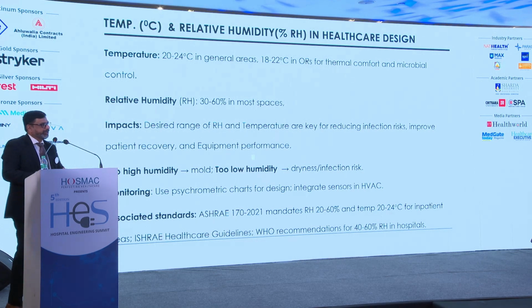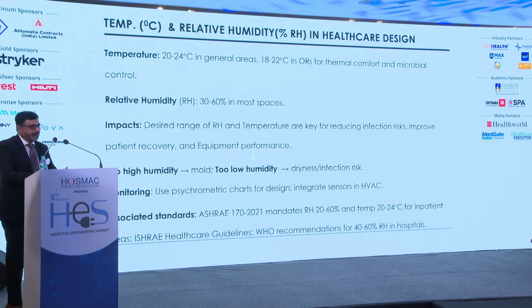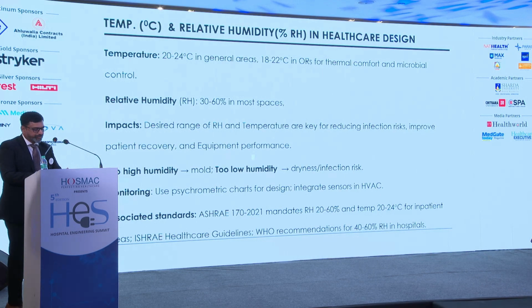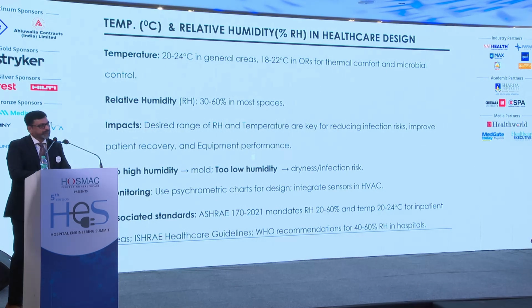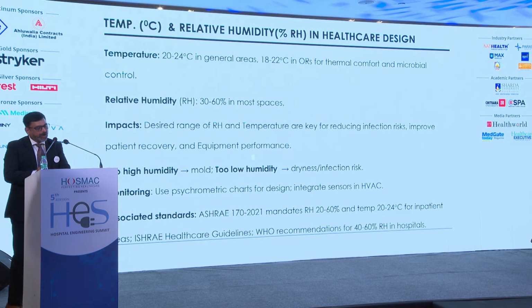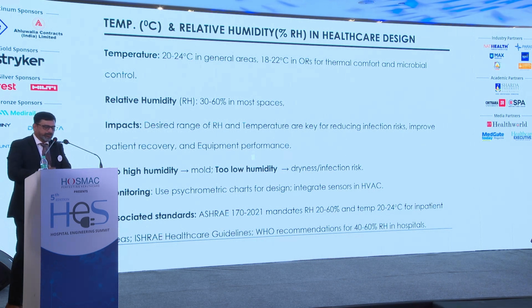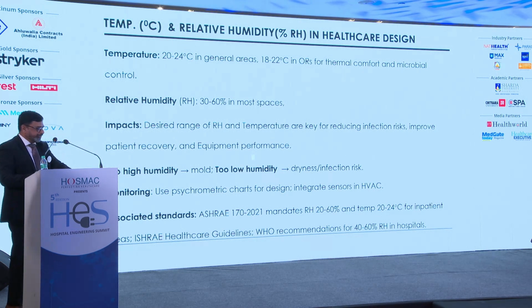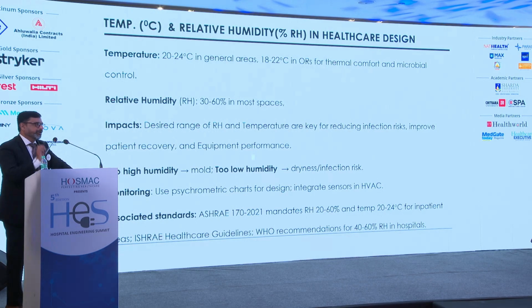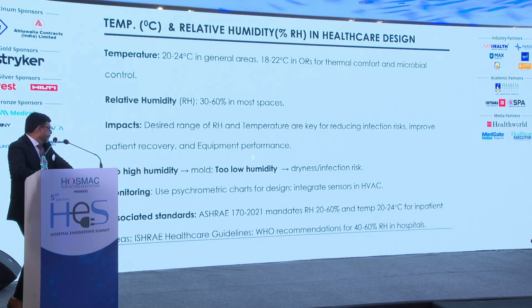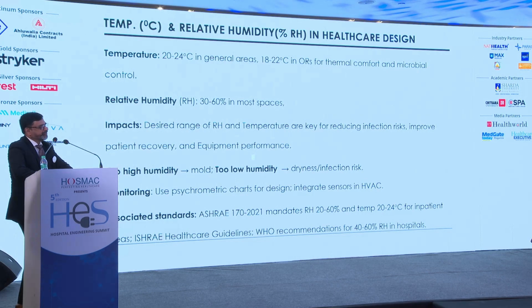So relative humidity is one of the major parameters for clinical spaces, because if humidity is high, microbial contamination is higher. That's why a temperature of 21 degrees centigrade is required, which avoids humidity going down to 50%. That's why we maintain this relationship between relative humidity and temperature. Whereas if you go with a temperature of 27 degrees in non-clinical areas, achieving 60 to 65% humidity becomes challenging as per the psychrometric charts.